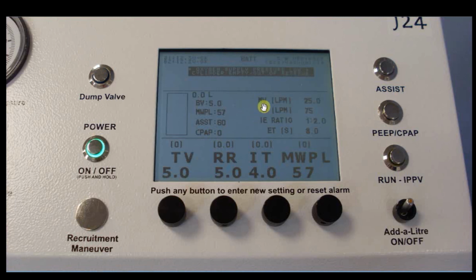Then on the right of this we have the minute volume, 25 litres. That's simply composed of the tidal volume times the respiratory rate. We have the inspiratory flow, 75 litres per minute, simply calculated from 5 litres delivered in 4 seconds. And we have the IE ratio as 1 to 2. We have 4 seconds of inspiratory time. We have a respiratory rate of 5, which is 12 seconds per breath, 4 of which are inspiratory time, so the expiratory time must be 8. So we have 4 seconds of inspiration, 8 seconds of expiration. We must have an IE ratio of 1 to 2.